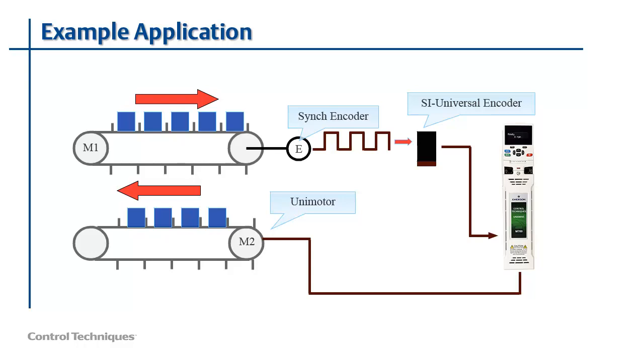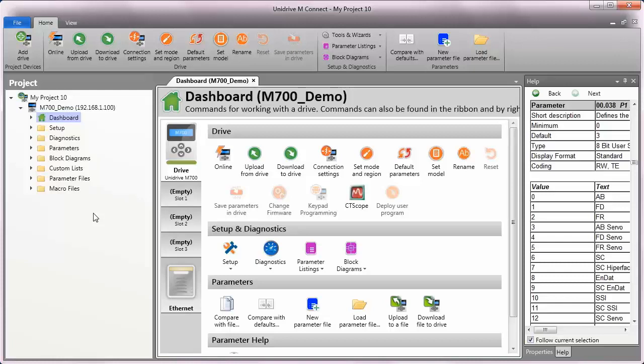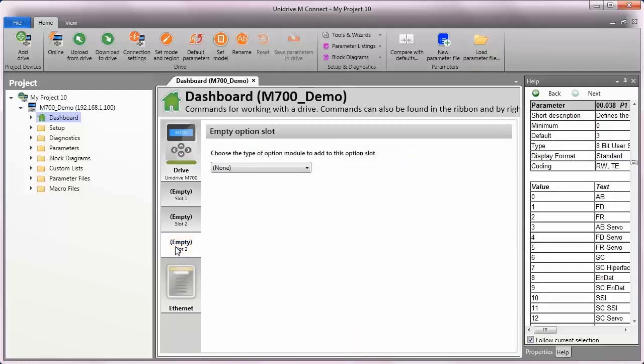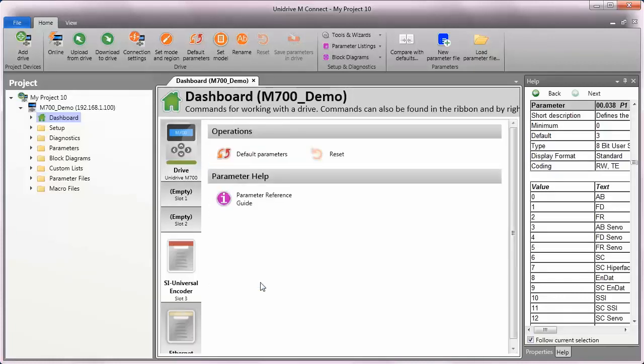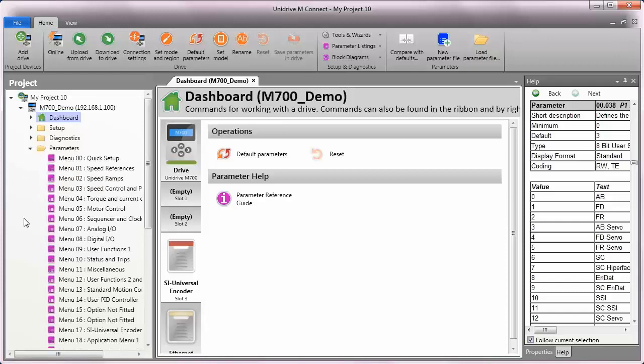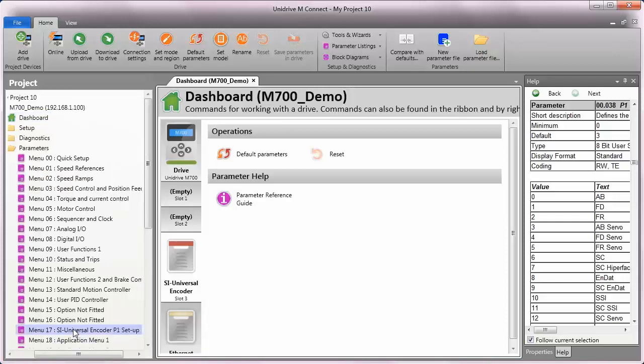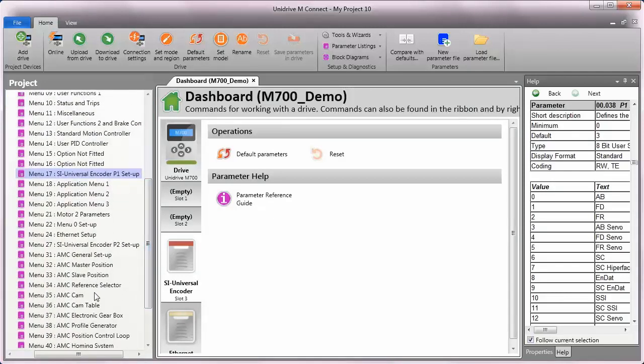Next, let's use MConnect software to configure the SI universal encoder module. I have a project started with MConnect software in which I've added my drive, I've added my motor, and I've got my motor feedback device configured as well. The next thing I need to do is I need to add the SI universal encoder module to my project. To do that, I'm going to click on slot 3, which is where the module is installed, and then I'll drop the list down, and I'll choose SI universal encoder. The SI universal encoder module has two ports on it, port 1, which is a high-density 15-pin connector, and port 2, which is a 10-position connector. I've wired the encoder from the conveyor into port 1.